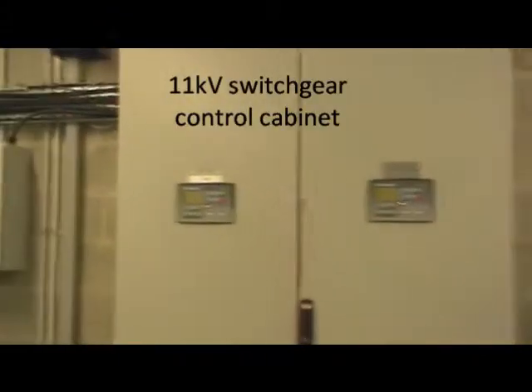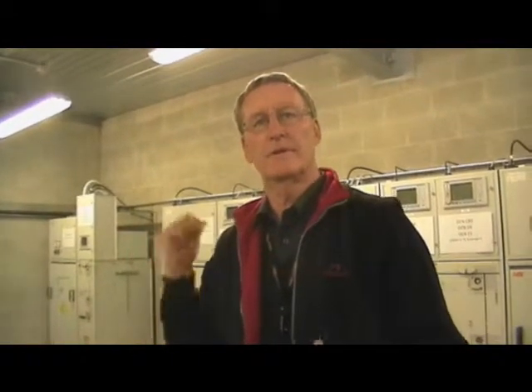So the hospital has an 11 kV ring going around 16 substations, or will be soon, and we have 2 injection ports from Well. They're both alive, but only one's switched in at any one time. If we lose that one, we automatically change over to the other feeder. If that's not available, the generators start. So your generators are plan C, so to speak. Yeah, plan B is the other main utility feed. The first 2 substations from the Well input, that's where we inject our 11 kV. I can show you that on the drawing.